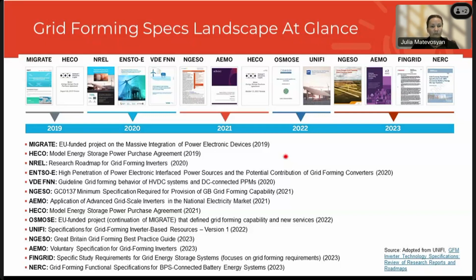The VDE FNN guideline is from Germany, and it provides a guideline for grid forming behavior of HVDC systems and DC connected power park modules. So this is more of a testing guideline. It has functional requirements, but also has some guidelines towards how they should be tested. National Grid ESO, the system operator in Great Britain, has developed grid code change 137, which is a non-mandatory minimal specification required for provision of Great Britain's grid forming capability. So that was approved in the beginning of 2021.